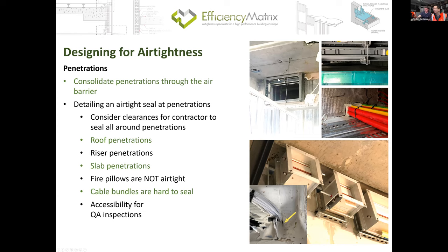Very commonly we can see, like this one, the duct is abutted to the surface of the concrete slab. Once you install it like that, you cannot go back to seal the top of the ductwork. If the duct is really small, less than 300 or 400 mil wide, potentially you can still use expanding foam or put an extended tube to put caulking on to seal it. But for common size 600 plus wide ductwork, virtually it is impossible.